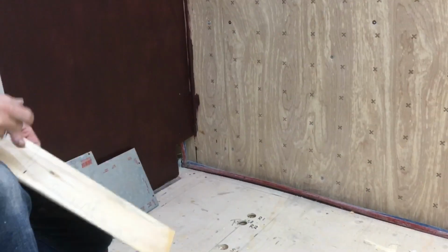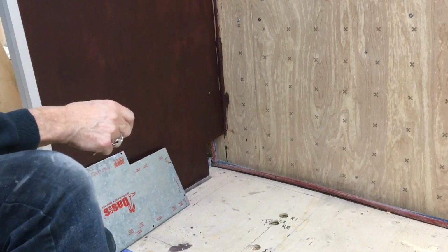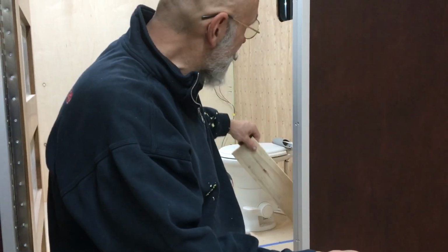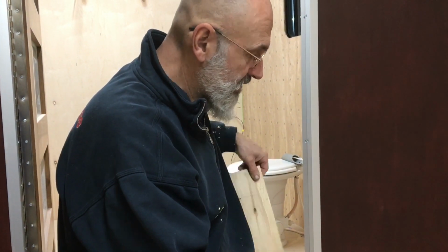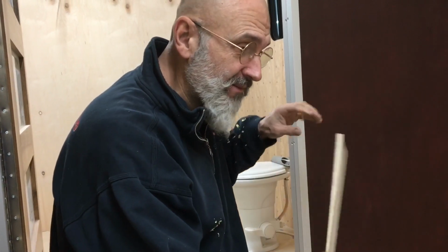L'autre réseau, le numéro 2, ça part d'ici, ça s'en va dans la salle de bain, ça s'en va dans la chambre à coucher, ça revient par le sous-sol pour chauffer où qu'on a nos réservoirs d'eau, ça remonte et finalement ça va passer dans le plancher radiant. La raison qu'on fait passer dans le plancher radiant en dernier, c'est l'eau d'un plancher radiant ne devra jamais dépasser 110 degrés Fahrenheit.